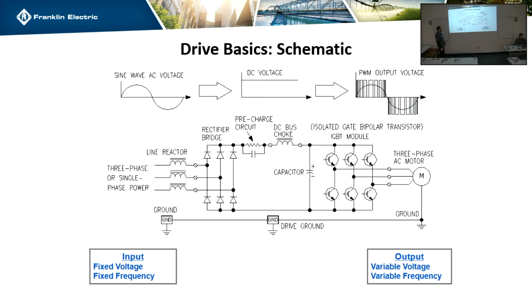So across the line, you're going full speed, and you don't have a choice. Once you have a VFD, it breaks it up for you so that you can control it. And this is the signal that ends up going out to the motor. So all of these are just on-off signals, and it changes how long it's on and off. And when it does that, it ends up getting a wave, and it tricks the motor into thinking it's an AC sine wave.